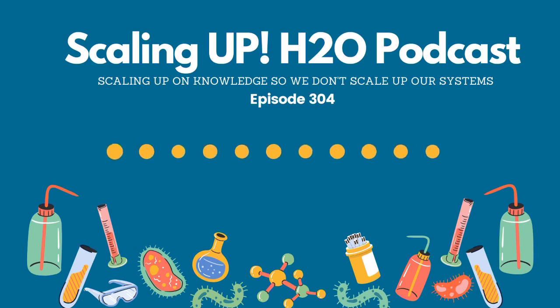Now, here's what pitting is. Here's how I like to define pitting. To go back, what general corrosion is, it's the only acceptable corrosion that we can have within our systems. And what that means is that all of the corrosion is taking place evenly over the entire metal surface. That's what these standards are referring to. A pit means a localized point on that piece of metal where the entire potential for that entire surface is taking place in that one little pinpoint, and that's called pitting. If you see pitting of any kind, it is not acceptable.